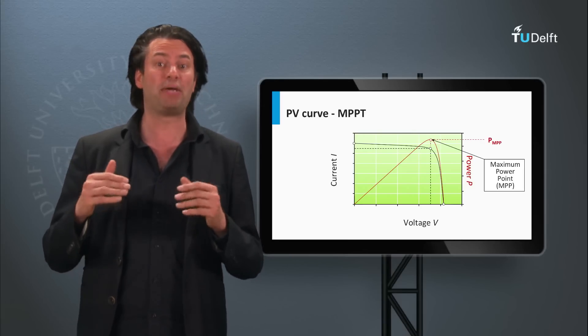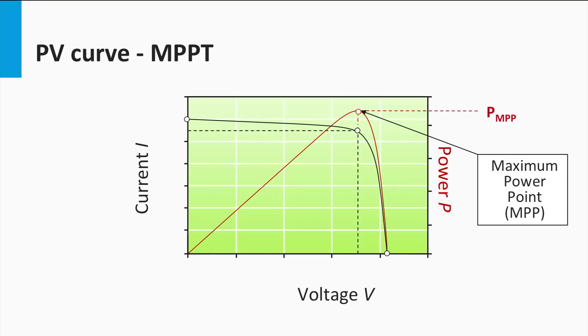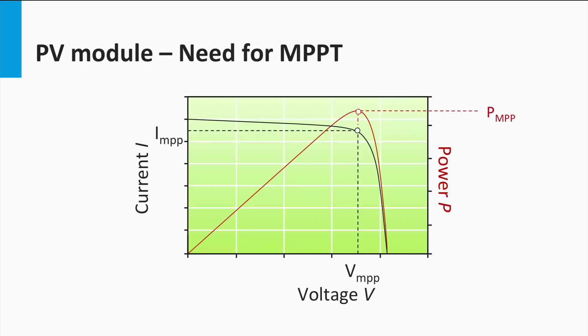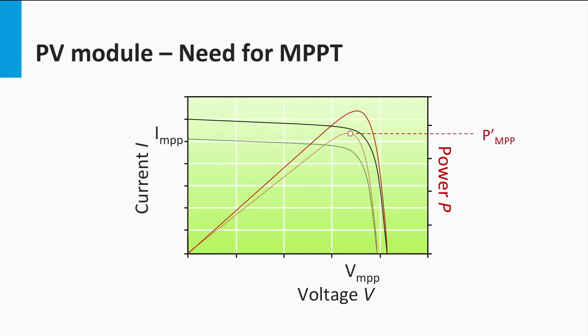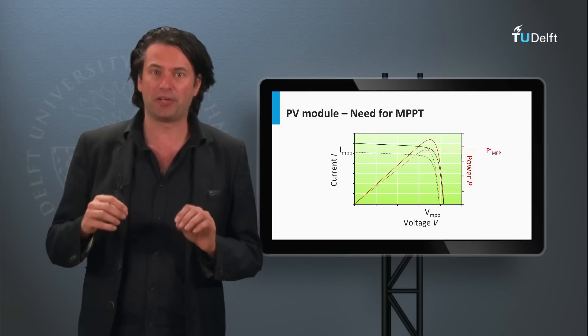The maximum power point corresponds to the peak of the PV curve or the knee of the IV curve. The simplest way to do this is to force the voltage of the PV module to be that at the maximum power point, or regulate the current to the right amount using converters. But what if, after forcing the PV module to operate at the maximum power point, the ambient conditions like irradiance or temperature change and in turn cause the IV-PV curve to change as well? This would mean that the old MPP is no longer valid. Thus, to be continuously at the maximum power point at all times, we would need to track any such changes in the IV curve and find out the new MPP. This process is called maximum power point tracking, or MPPT.